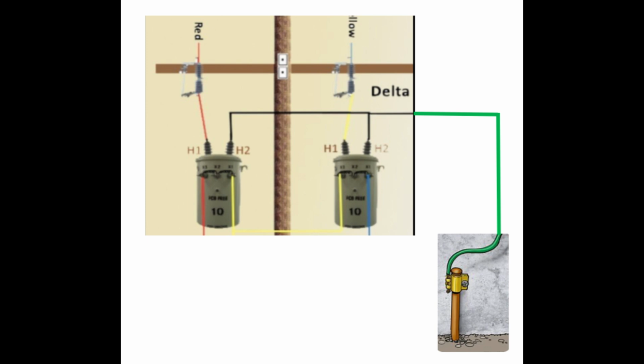The figure shown is an open delta connection of two 10 kVA transformers. The apparent power capacity of this connection is 17.32 kVA, considering the 10 kVA rating of each transformer. Noticing the two primary wire sources used, the red and the yellow leads are the phase conductors which are connected to the H1s of the transformers, while the H2s are connected to earth. Therefore, the primary voltage of this system is the line-to-line system voltage divided by the square root of 3 of the source substation. This displays the flexibility of the three-phase system over the single-phase counterpart.